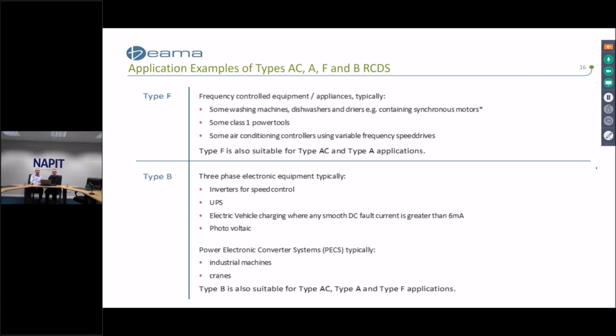And as you can see under the Type B, which I didn't run through, there are a number of areas there: inverters for speed control, UPS systems, electric vehicle charging, as I mentioned, where any smooth DC fault current is greater than 6 milliamps, photovoltaic systems, power electronic converter systems, typically industrial machines and cranes. And just to recap, Type B is suitable for Type AC, Type A and Type F applications. Now handing back to Paul again.